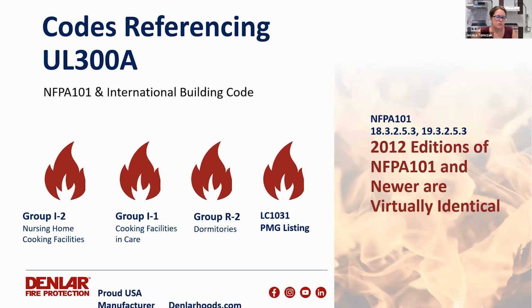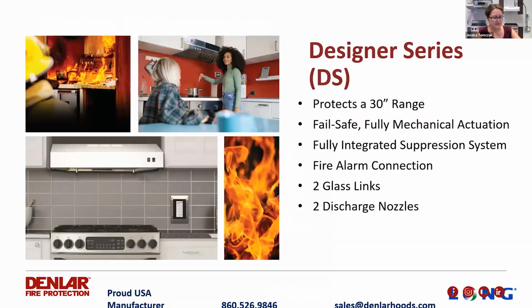They require a UL 300A suppression hood, a minimum of 500 CFM, a manual pull station, a fuel source disconnect, and you also have to have a 120-minute interlock device. So what we do is package all of those things with our D1000 to provide an NFPA 101 compliant version, and we call it our NFPA 101 upgrade. You'll see a lot of those things in places like healthcare facilities and long-term care.